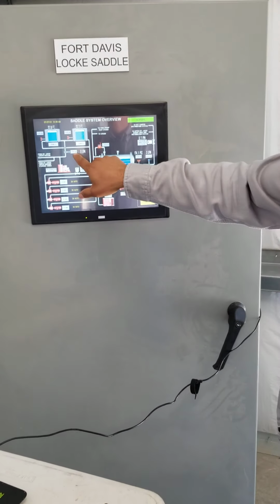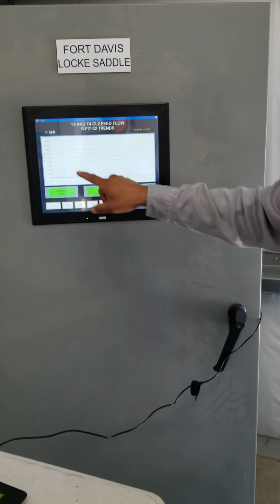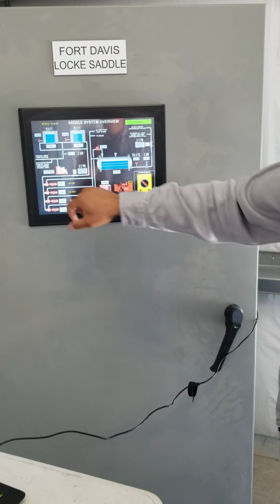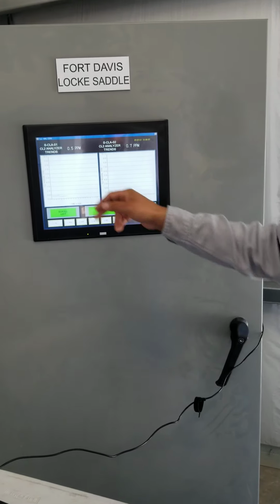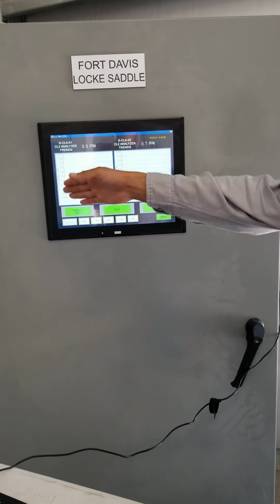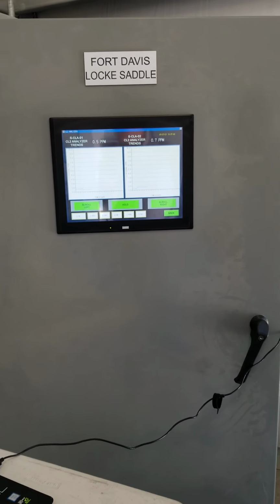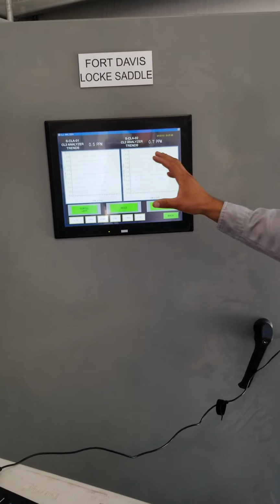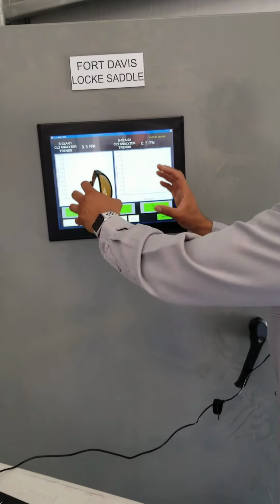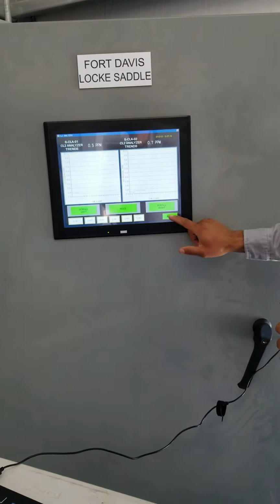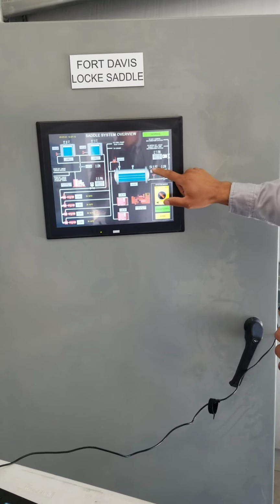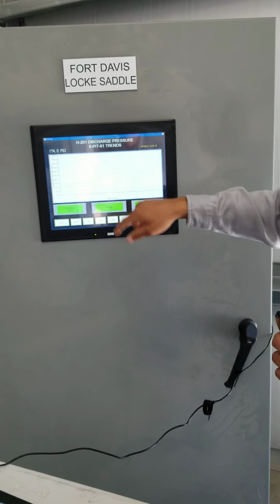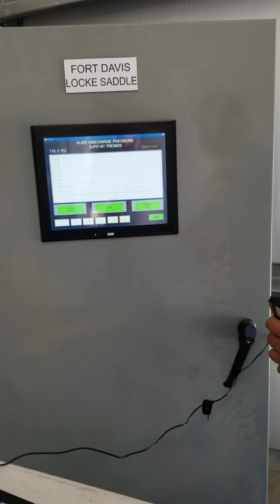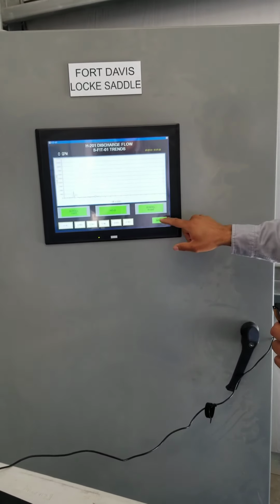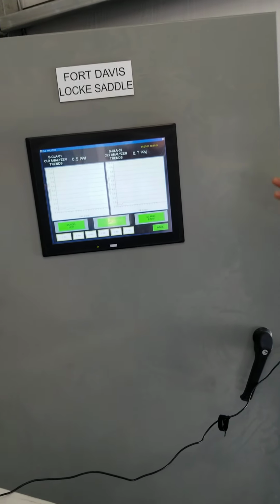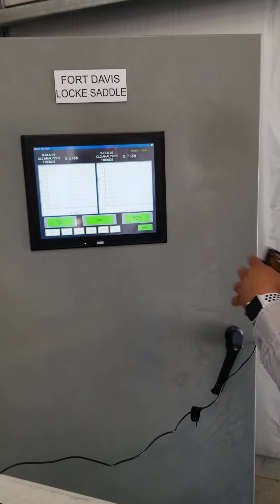It has that feature. Here's your flows. Here's the chlorinator, right here, analyzers. So I have them both side by side. So you have your before and your after. And it works exactly the same way to access the trends. But since it works in pairs, you would put the time, and it'll take you to both trends at that time. Good deal. There's also this pressure. Here's a pressure indication. Same thing. Flow, same thing. Analyzer. It's the same screen, but I just have it on the other one. Either or analyzer.